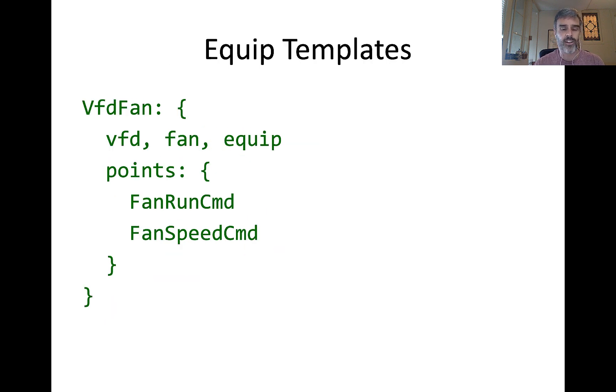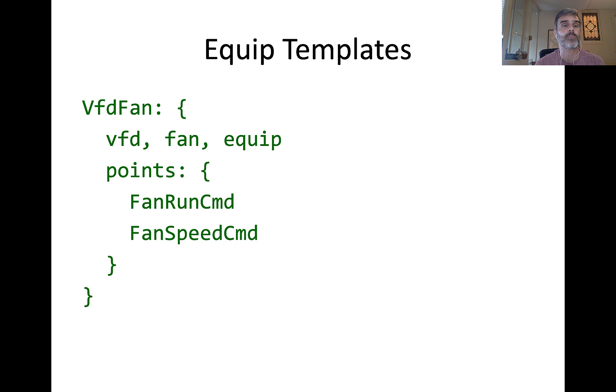We're going to look at this in detail in some of the videos, but this is a very simple equipment template showing what an equipment type might look like. You can see here I've given it a type name. This particular template, which is a VFD fan, requires the VFD tag, the fan tag, and the equipment tag. And then I'm requiring two specific point types: a fan run command and a fan speed command. Those would be somewhere else in your library. This is just to give you a quick overview of what a particular equipment template might look like.